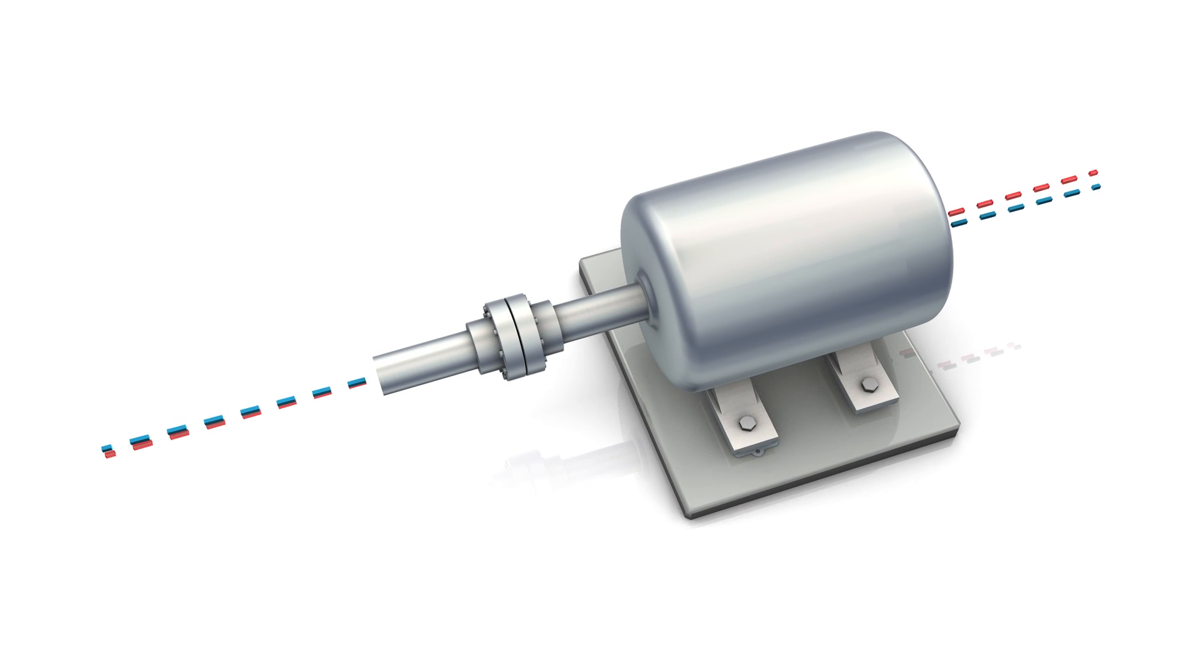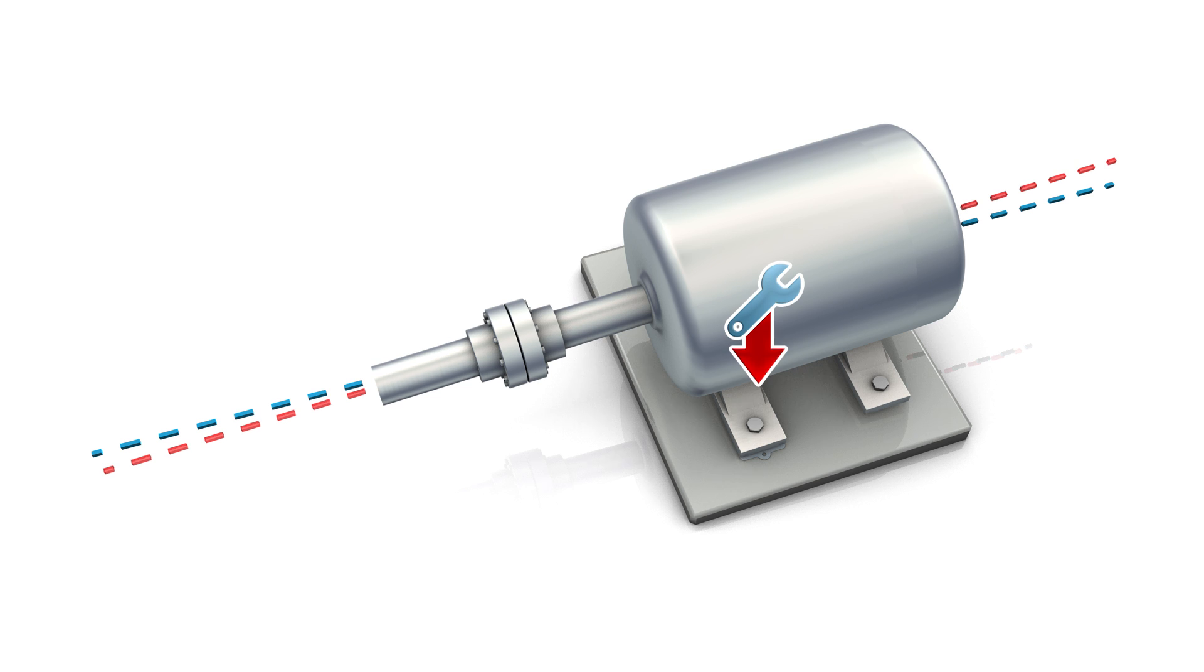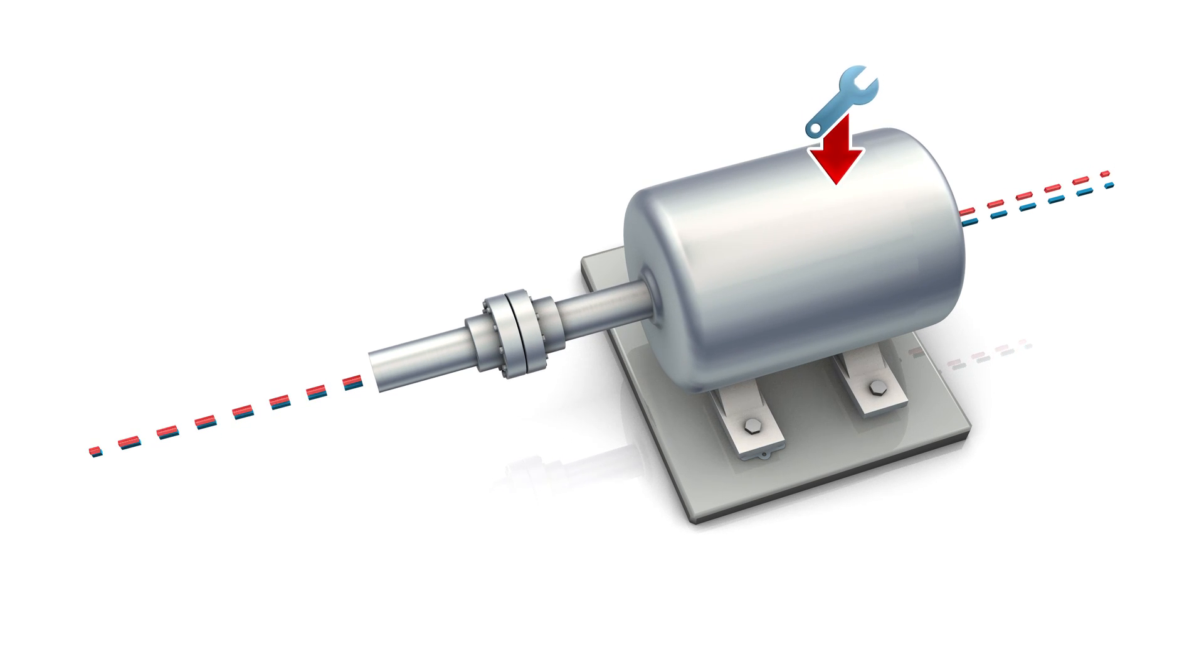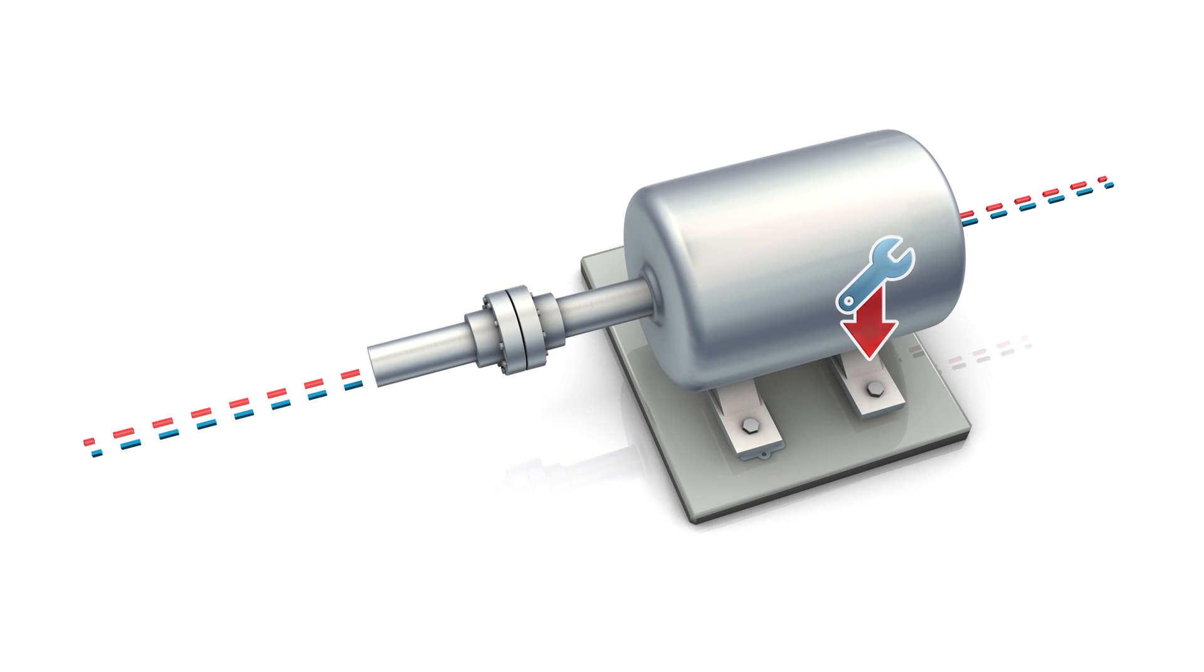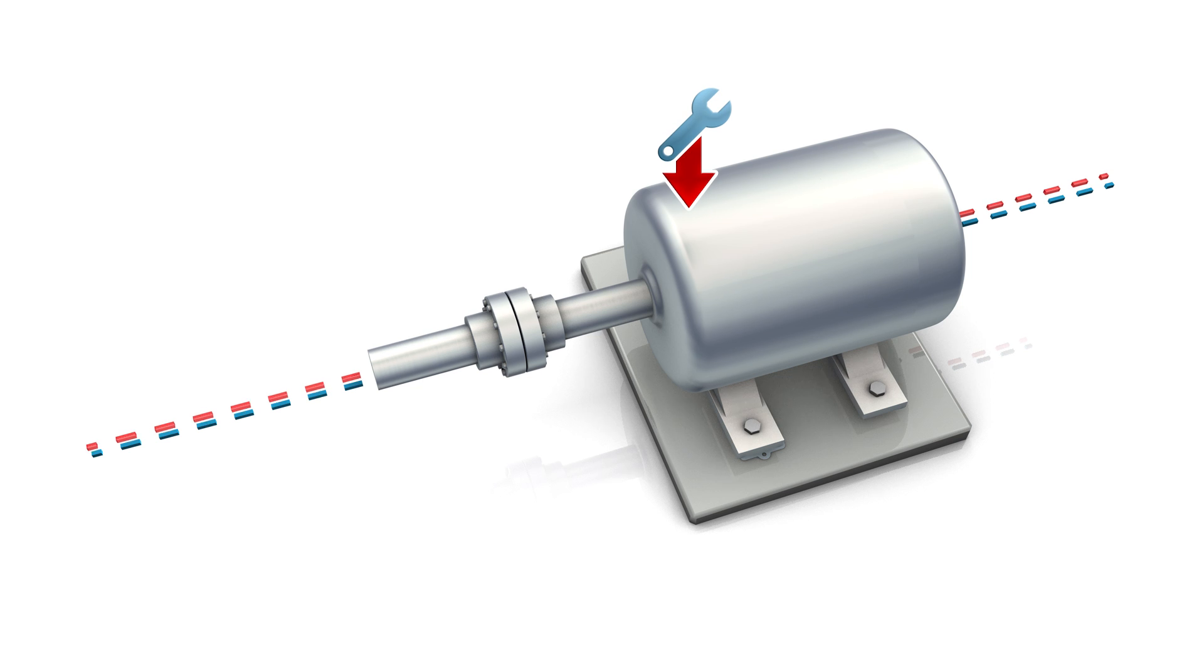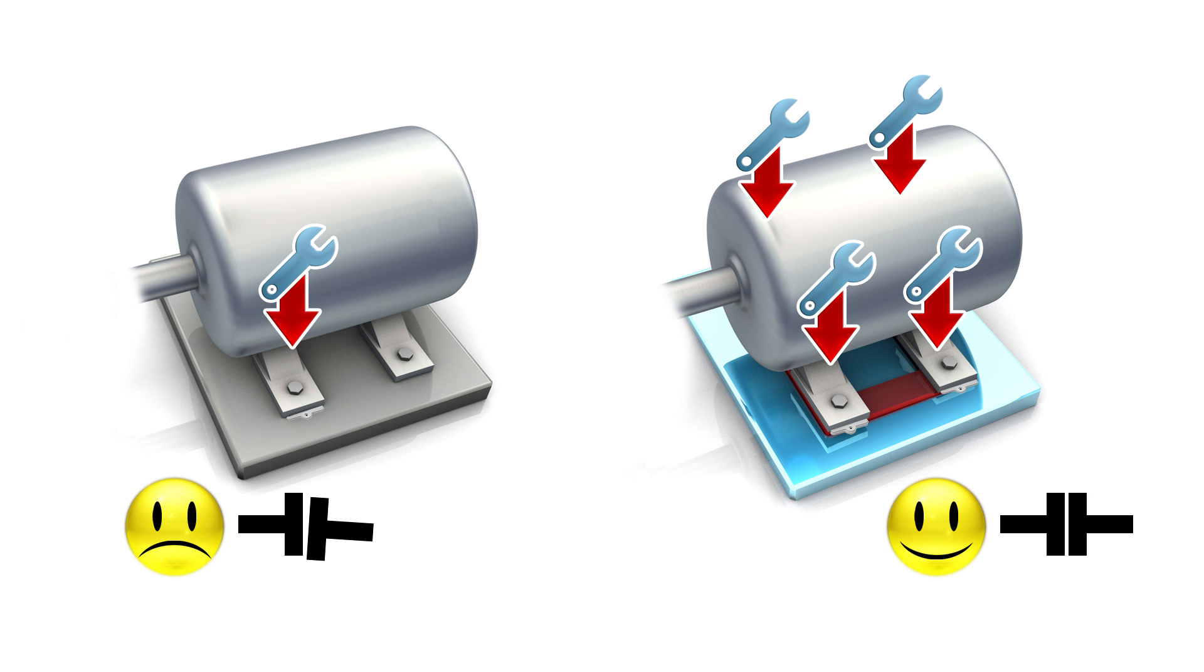Soft foot makes moving a machine more difficult. The retightening of each bolt will alter a shaft centerline and can make accurate axis alignment nearly impossible. Remember, to overcome soft foot you have to consider adjustment of a whole machine frame, not just one leg.